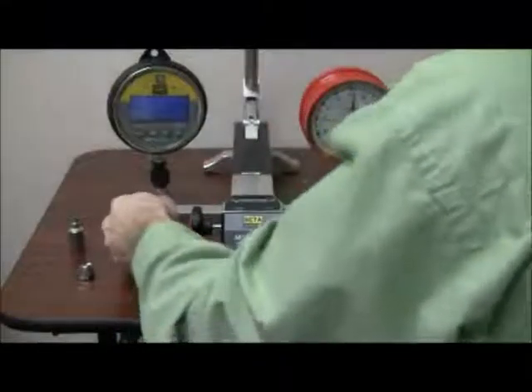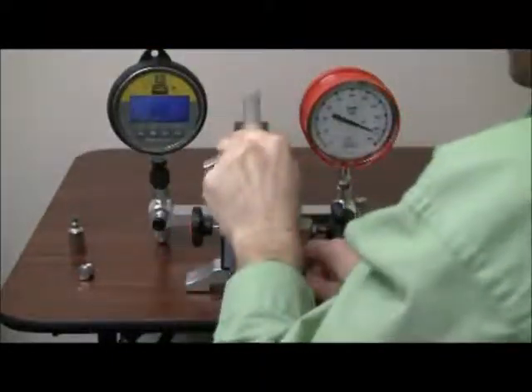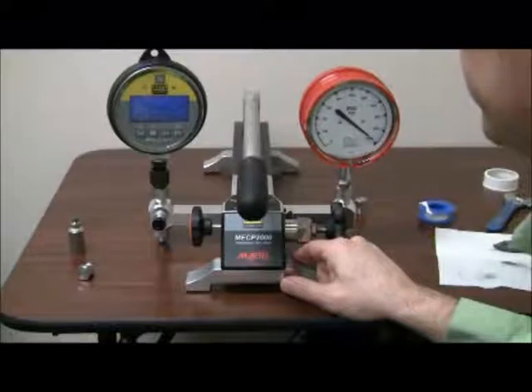In this test, we're just going to go up to full scale which is 200 psi. Once again, I'm checking for leaks, making sure everything is tight. Now it will take some time to settle, but as you see here, we will not have any leaks present.